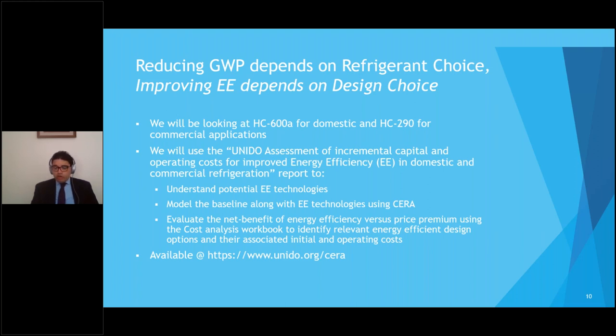Reducing global warming potential depends on the refrigerant choice. Moving from R134A to isobutane (HC-600A) gives an almost 1000-fold reduction in global warming potential. However, improving energy efficiency depends greatly on design choices. In our study, we looked at isobutane or hydrocarbon 600A for domestic appliances and propane or hydrocarbon 290 for commercial applications. We modeled the baseline along with energy efficiency technology options using CERA, then evaluated the net benefit of energy efficiency versus price premium using cost analysis workbooks. These models are available at unido.org/cera.